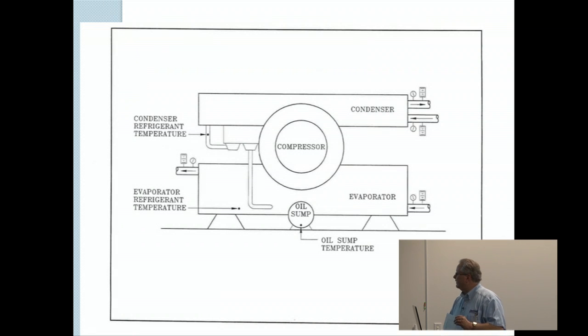Here's a pictorial of an old Trane centrifugal chiller. Again, you have your temperature and pressure gauges on both the entering and the leaving on the condenser. The same for the evaporator. You want to get a refrigerant temperature on the condenser and for the evaporator, and an oil sump temperature, particularly if you have a separate oil management system on your chiller. Not all chillers have that.